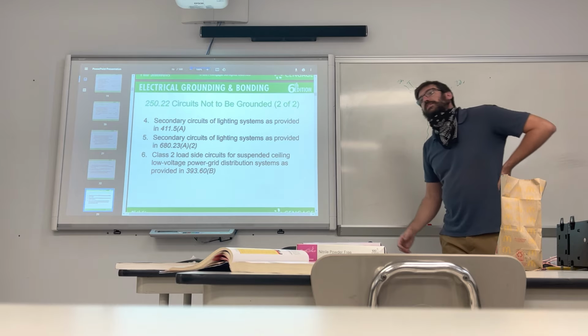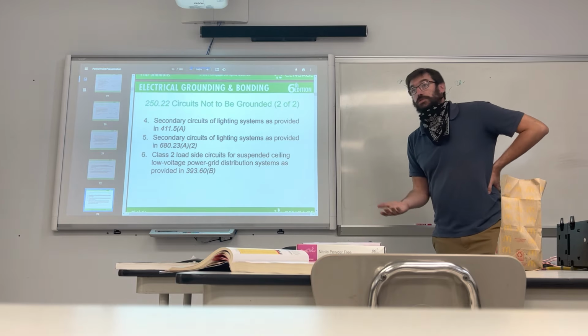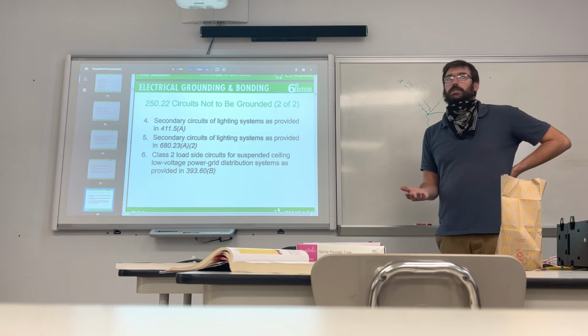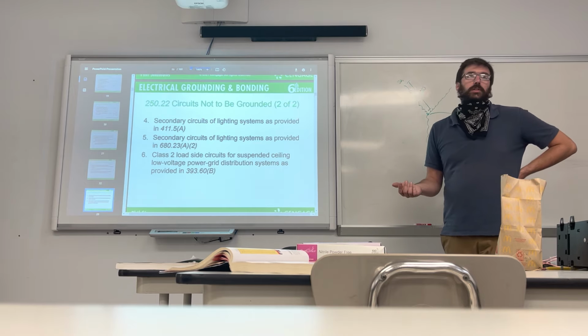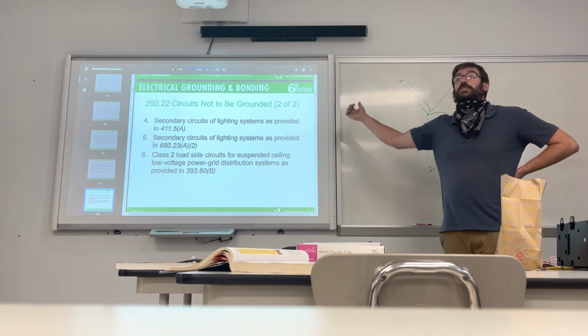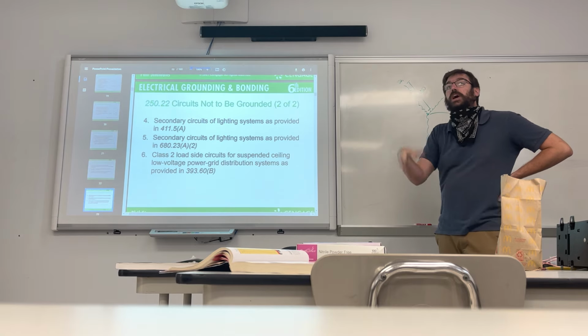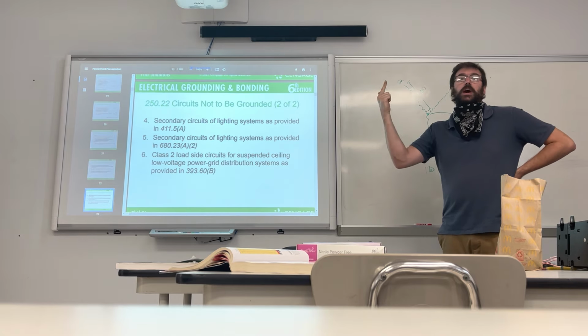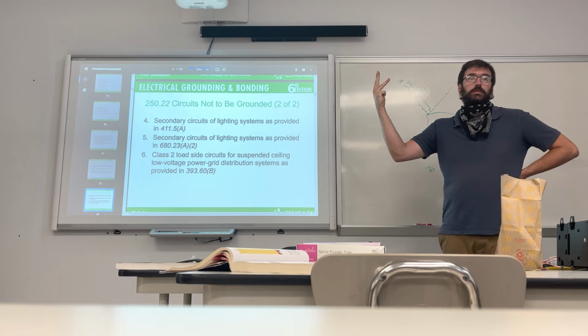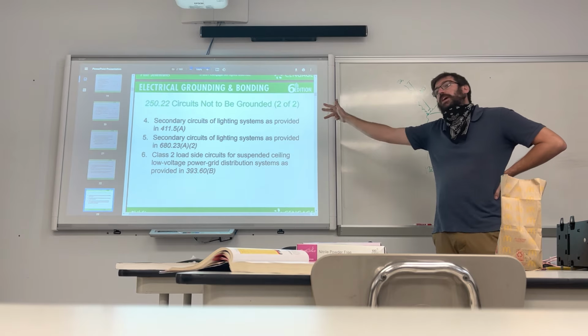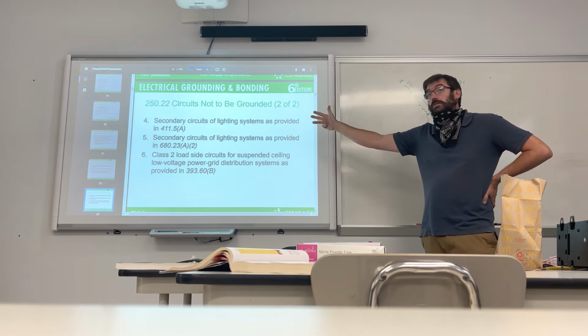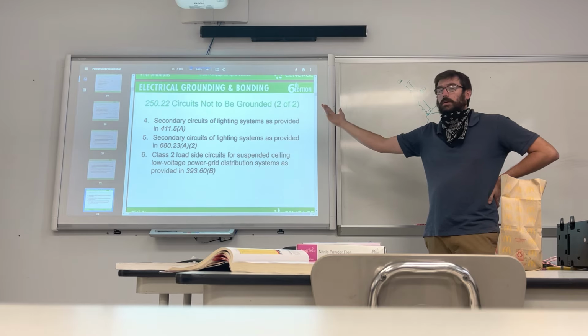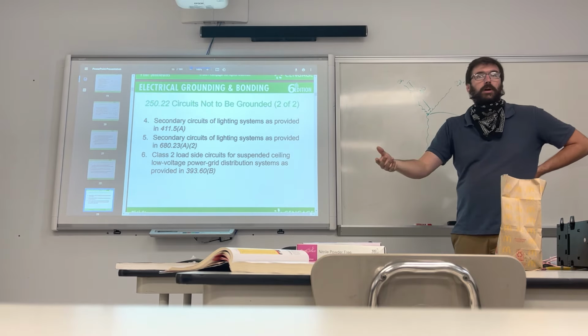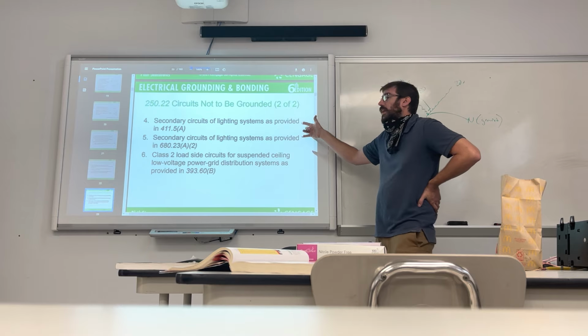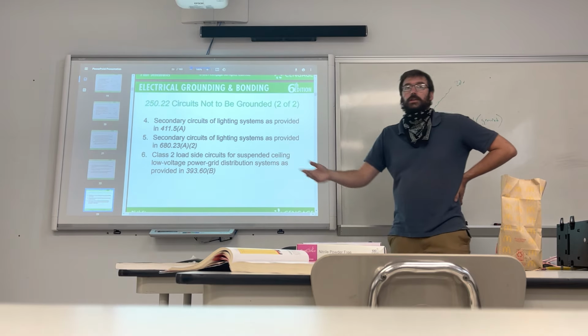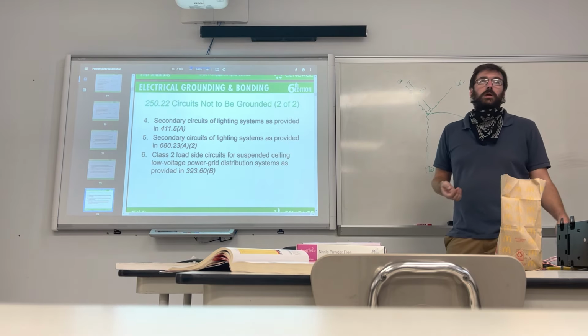So normally if it's stepping down to less than 30 volts, which normally LEDs are operating at way less than 30 volts, it doesn't have to be grounded, because that's a secondary system off of a system that's already been grounded, right? When you supplied this system with power, did you not bring a hot, a ground and a neutral to it? Sure you did, right? In that box you hooked it up to, you hooked the ground up to that box, didn't you? So there's not much more trouble that can happen upon that. You just can't and don't have to ground past that, because it's just getting stupid at a certain point.